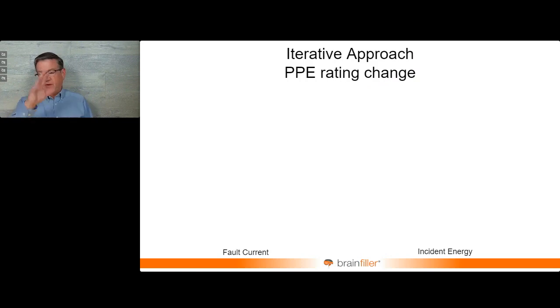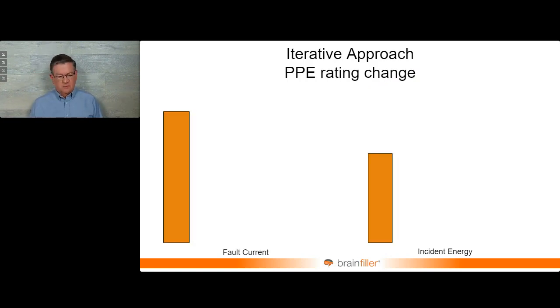So I have a method. This is something I developed a long time ago. I wrote the first book on arc flash studies way back. And if you don't know what the short circuit current is from a utility, use an infinite bus calculation. And you might think, wait a minute, you can't do that. That's not worst case. Infinite bus may not be worst case, but it might be.